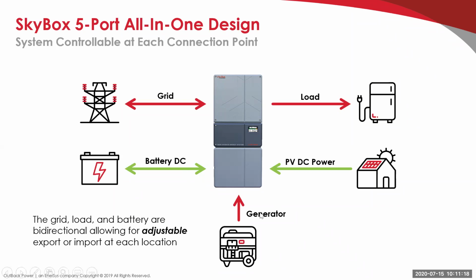Comes with the load center, but the Skybox itself is a 5 kW unit that has all that capability without needing any external charge controllers or communication equipment. It is a transformer-less inverter charger, 5 kilowatts, but it's real nice and slick and very simple to install. It can be used off-grid, but we really don't recommend it because it's transformer-less and therefore doesn't have any surge capability. But it's a really nice, slick evolution of what Outback has always had, putting everything into a single housing to make it simple.